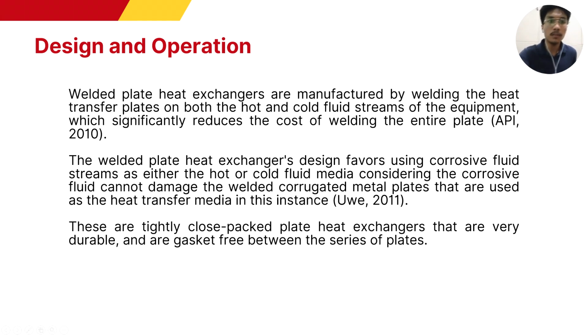First, welded plate heat exchangers are manufactured by welding the heat transfer plates in both the hot and cold fluid streams of the equipment, which significantly reduces the cost of welding the entire plate, according to API 2010. The plates are basically welded on both the hot and cold fluid streams, or the pathway of the fluid coming in and out of the plate heat exchanger. Also, the gaskets on these plates are non-existent because the plates themselves are already welded. This then results in a much lower cost of the overall equipment.